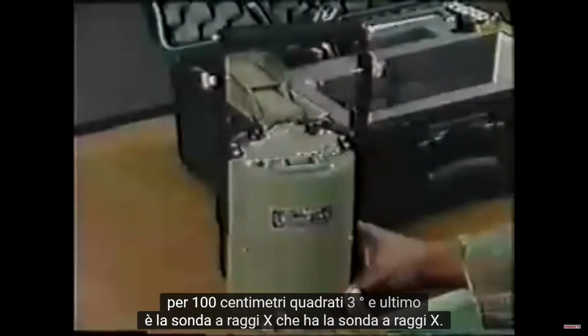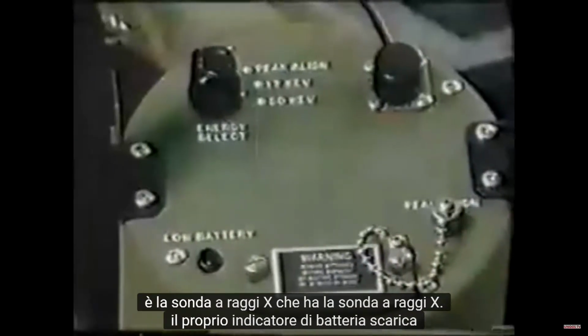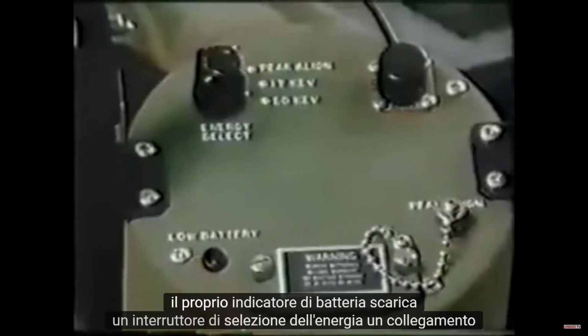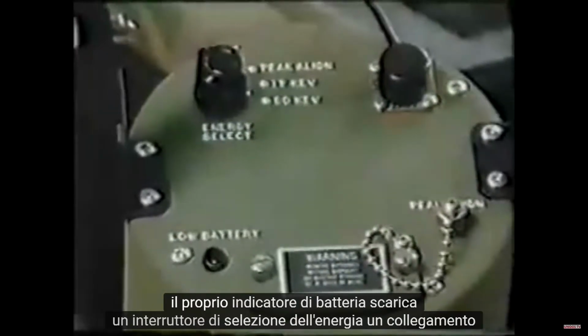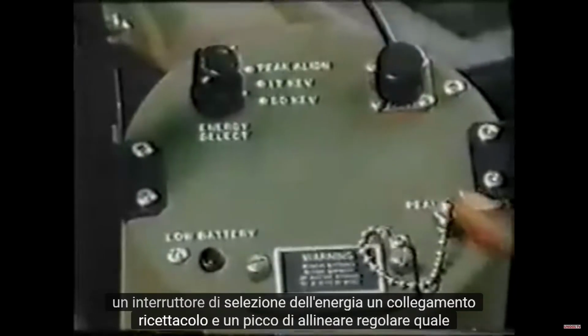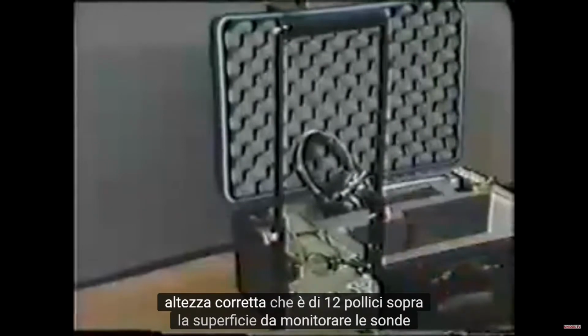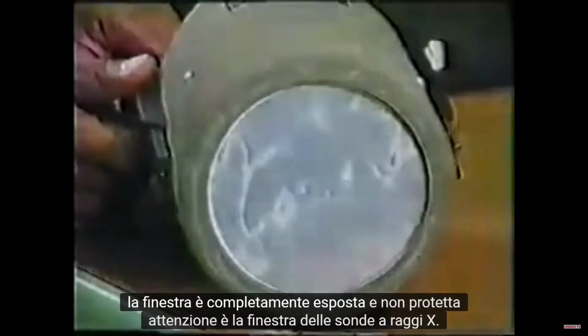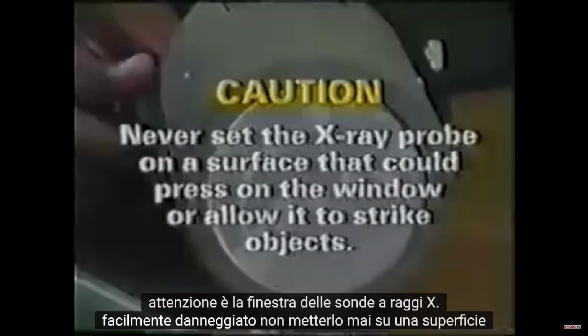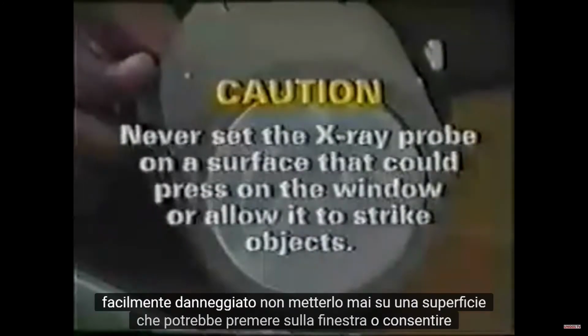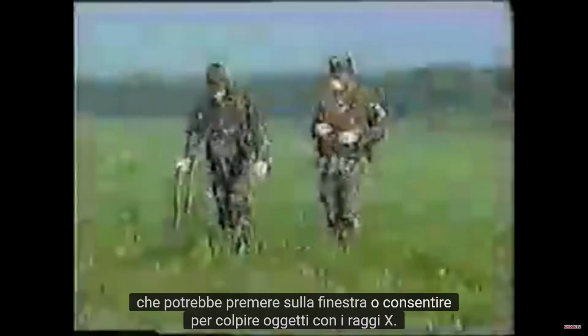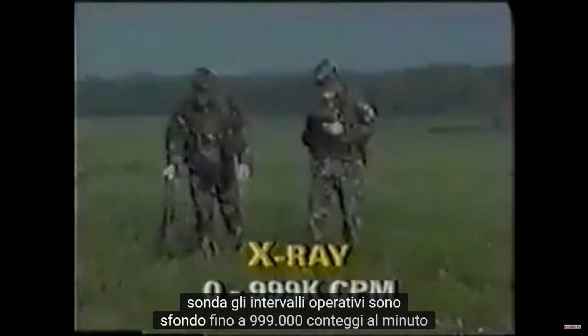Third and last is the X-ray probe. The X-ray probe has its own batteries, low battery indicator, an energy select switch, a connecting receptacle, and a peak align adjust, which is used only in extreme cold. The handle is adjustable to place the probe at the correct height, which is 12 inches above the surface being monitored. The probe's window is fully exposed and unprotected. Caution: the X-ray probe's window is easily damaged. Never set it on a surface that could press on the window or allow it to strike objects. With the X-ray probe, the operational ranges are background to 999,000 counts per minute.